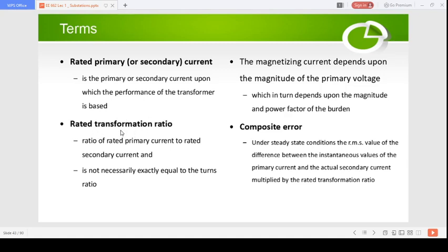Next, the rated transformation ratio: the ratio of rated primary current to rated secondary current is known as the rated transformation ratio. It's a typical thing that you talk about with transformers. This may not necessarily be exactly equal to the turns ratio, because some saturation happens and the relationship is no longer linear for high currents. Because of that, the ratio may not be the same as the turns ratio. The magnetizing current depends upon the magnitude of the primary voltage, which in turn depends upon the magnitude and power factor of the burden. Burden is the load.